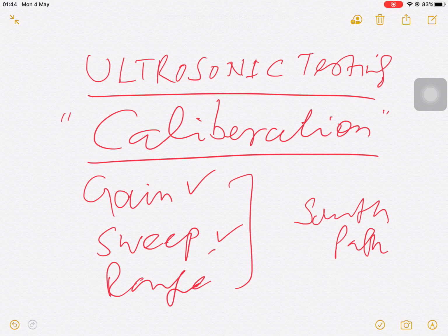Horizontal linearity is the measure of the uniformity of the sweep speed of the instrument. The instrument must be within the linear dynamic range of the sweep amplifier and associated circuitry for electron beam position to be directly proportional to the time elapsed from the start of the sweep. It may be checked using the multiple back echoes from a flat plate of a convenient thickness.